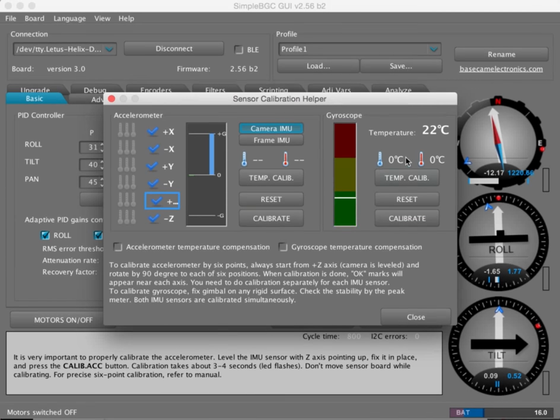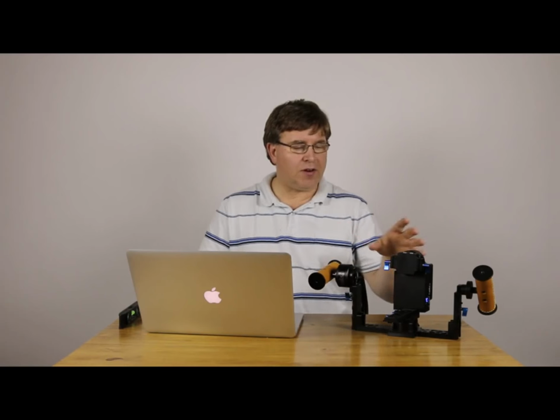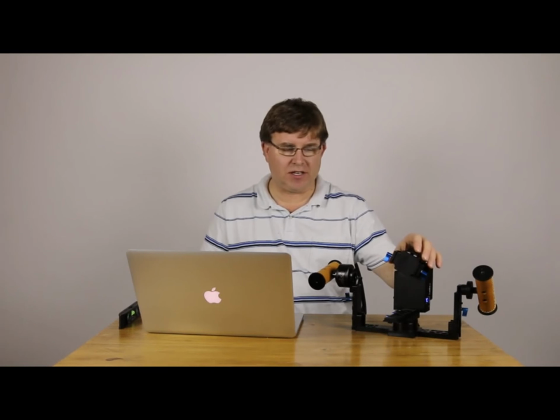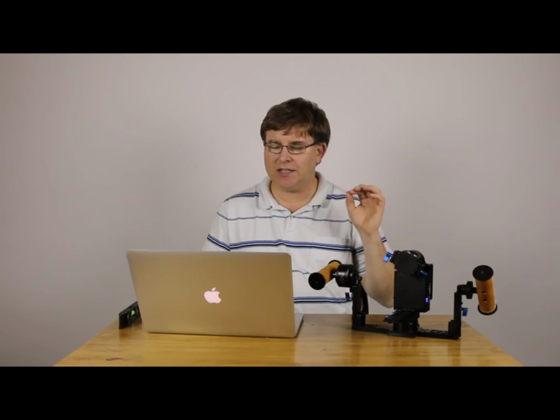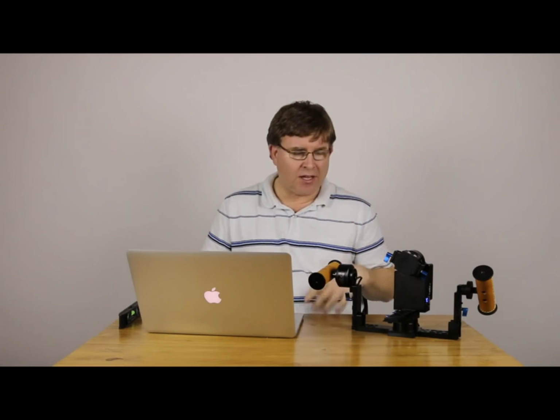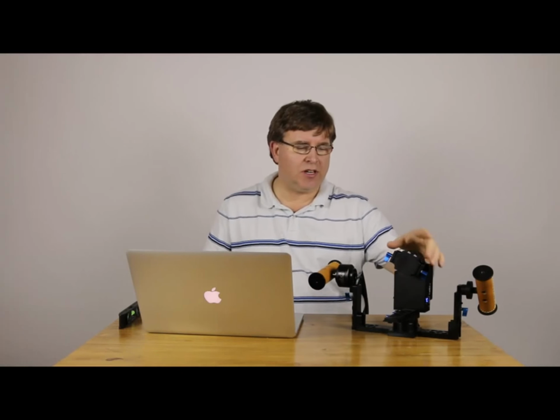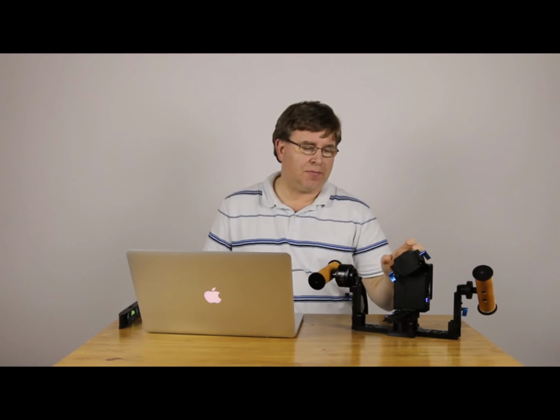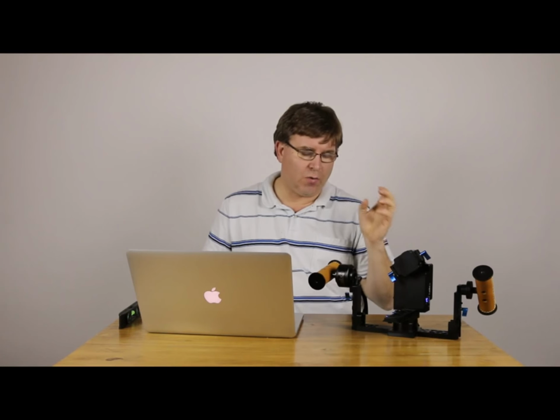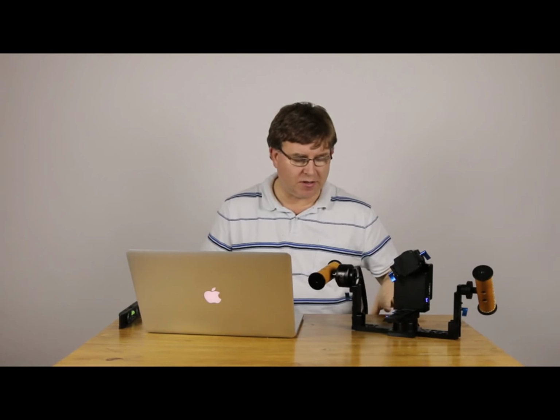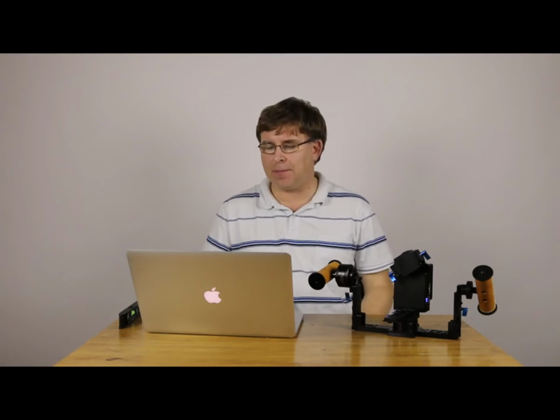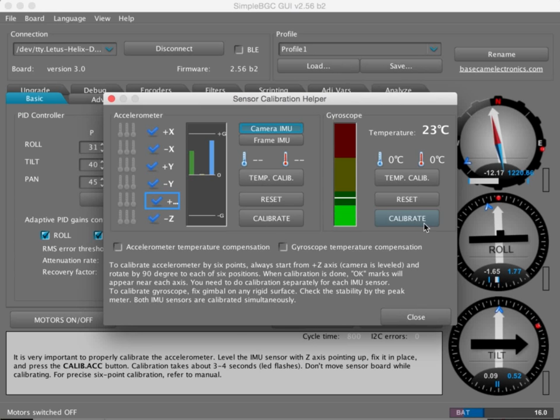And so I'm going to just calibrate the gyros first. I don't have to have a specific orientation for this. I just have to have it completely stationary for 5 or 10 seconds before it gets started. So I can have it in this orientation, I can have it over here, but you just want to make sure it's not moving. It's really important to not have the motors on because this thing is extremely accurate and you want it to be completely stationary. Don't be putting your hands on the table or anything like that. I will go ahead and hit the calibrate button here.